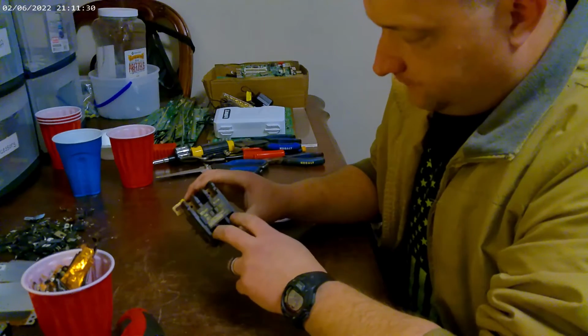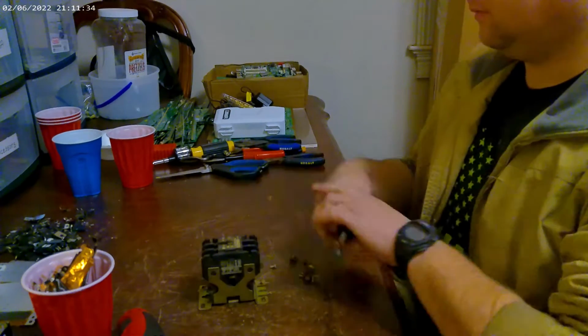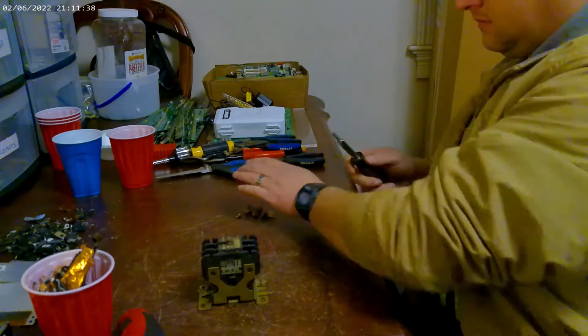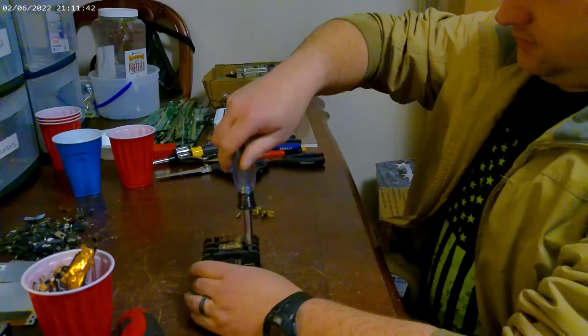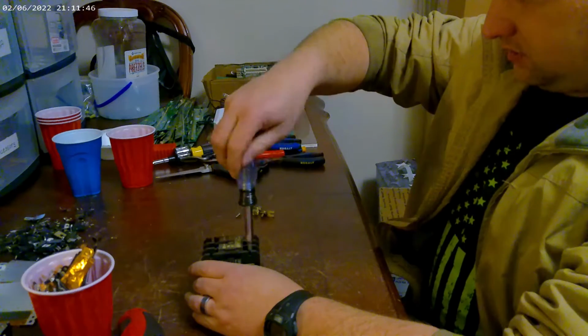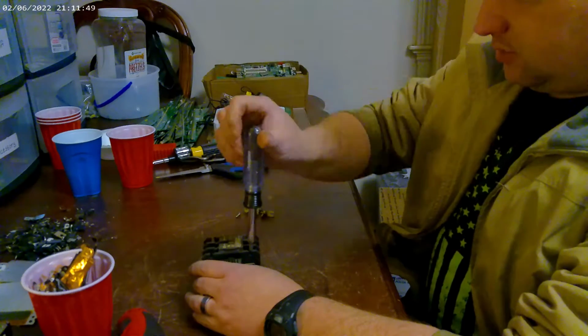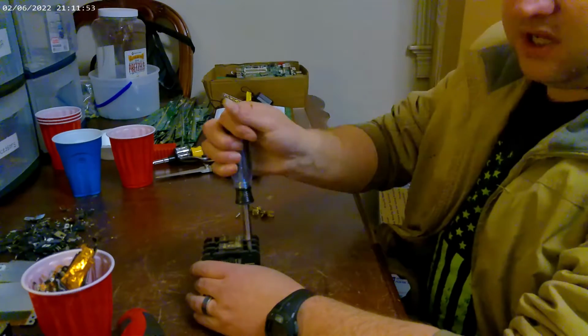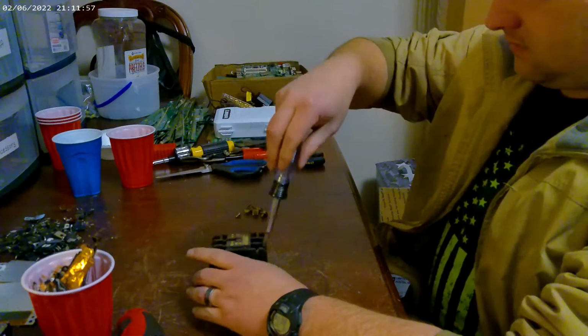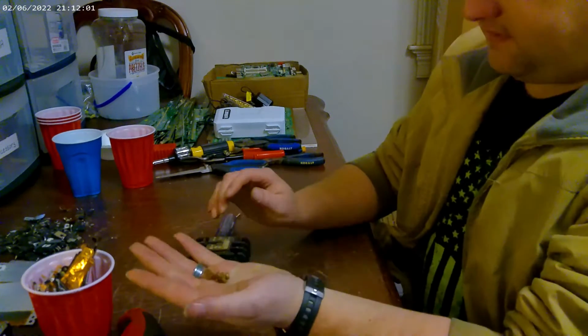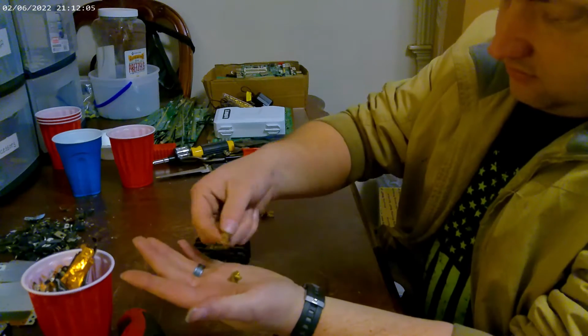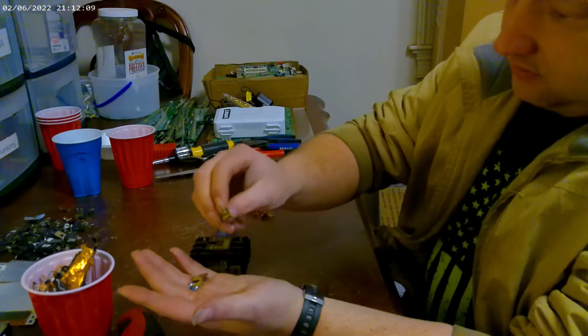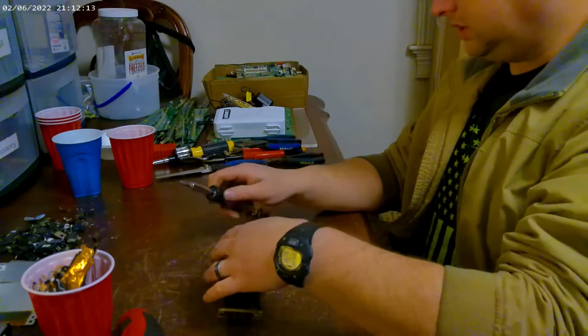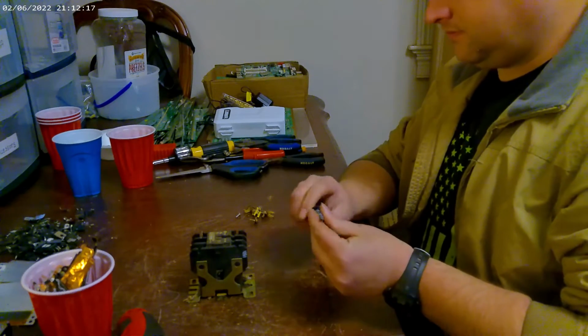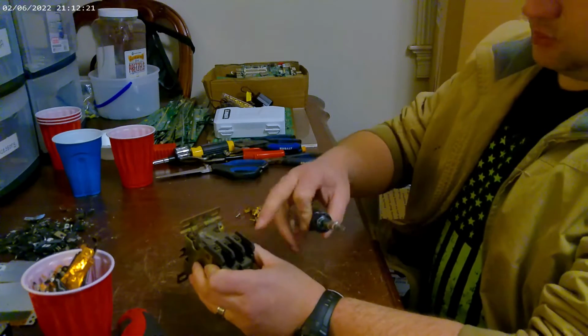Alright, so off the top up here, I've already taken these three out. I've got one left. So you spin it out counterclockwise. Most of the time, right there, see it stops. If you put a little bit more pressure on it, it'll come on out. That's just kind of a safety feature to keep them from backing out and the screws falling out. Once you get it backed out, you pull this stuff out. All this is brass, so it has to be kept a little separate. Your low voltage side, I already took one out, and again this is brass, so you take the other one out.